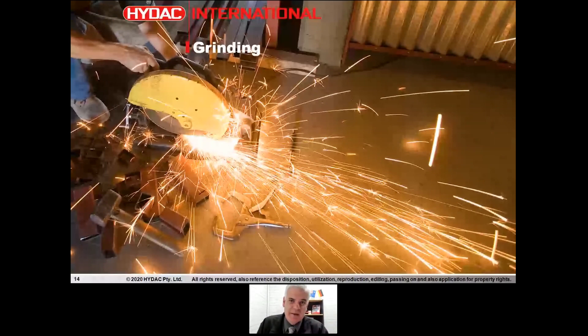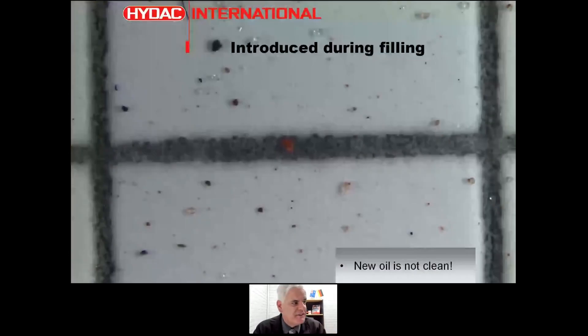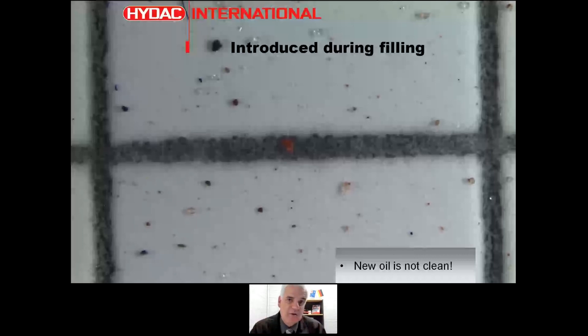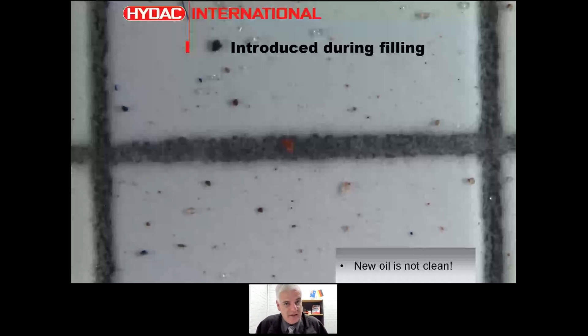Another source of contamination is during the filling of the system. It's obvious to people involved with fluids that new oil should be clean — but the funny thing about hydraulic and lubricating systems is that the fluid, brand new out of a drum, will usually be much dirtier than it will be for the rest of its life if the system's working the way it should. Basically, new industrial lubricants are too dirty to put into a hydraulic or lubricating system, so as we fill a system we've cleaned, we can contaminate it again.